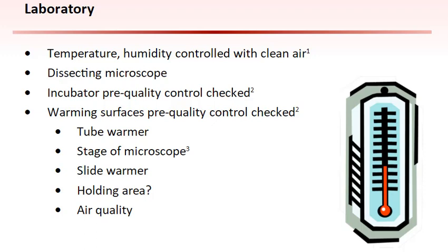controlled conditions. The embryology laboratory where oocytes will ultimately reside should be equipped with incubators that have undergone quality control to assure that their temperature, gas concentrations, and humidity are within tolerable ranges specified by the laboratory.